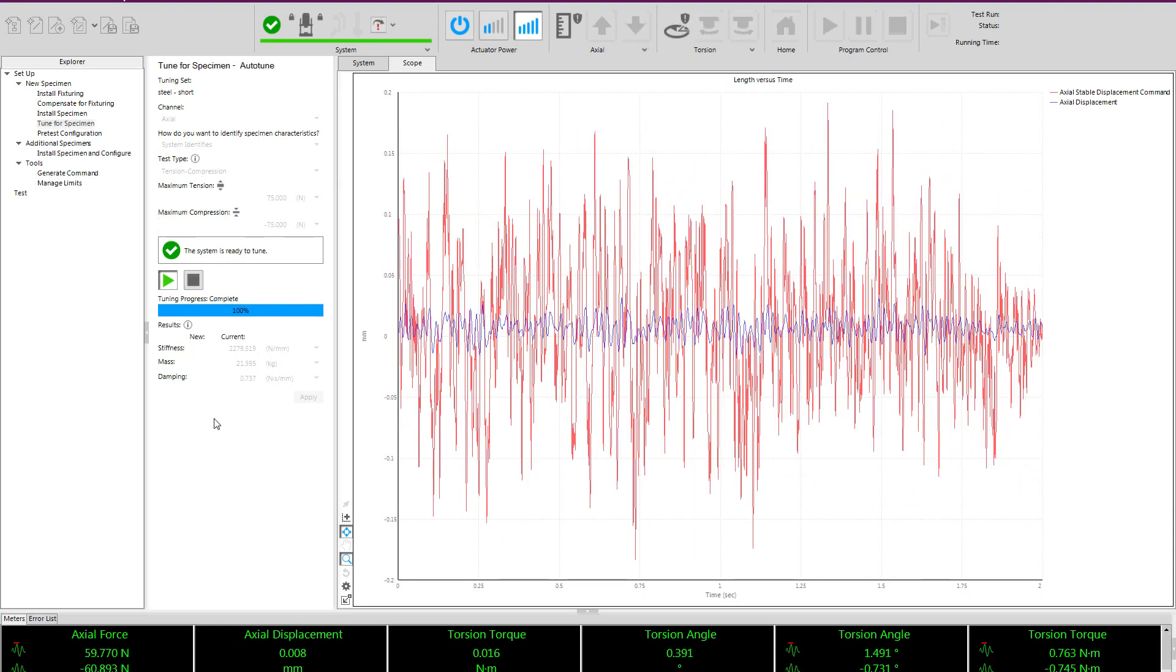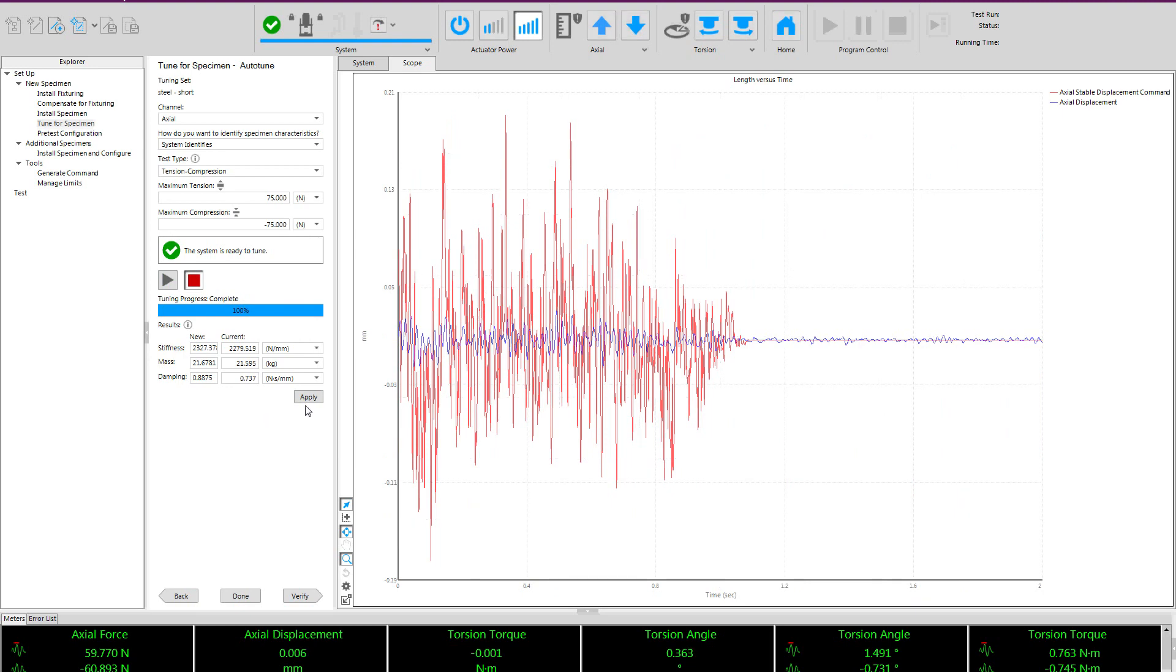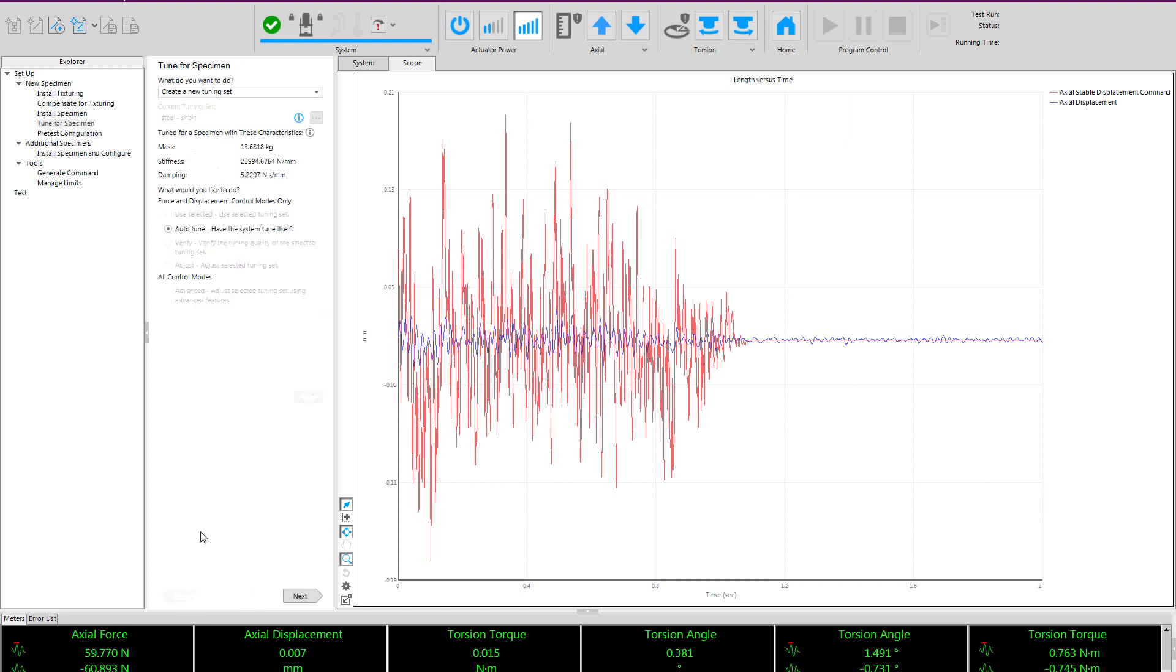You can see the procedure executes for axial the exact same way as it did for torsion. I'll apply these tuning parameters. And now again, I have multiple options. I can verify, I can be done and save my tuning set, or I can go back for a few additional options.